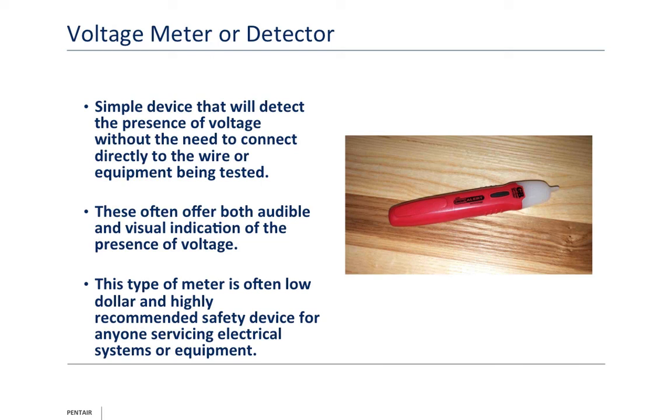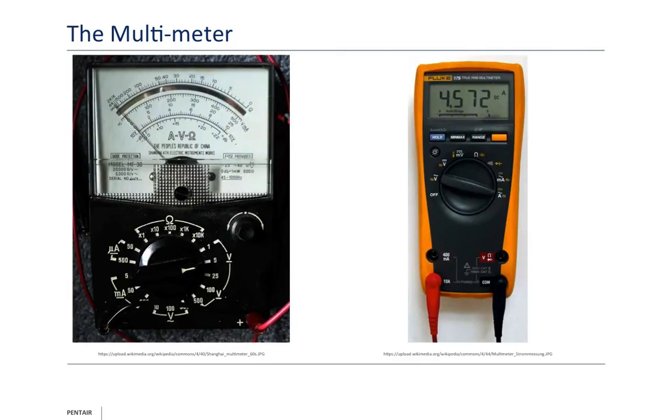When in doubt and you want to make sure, break out your voltmeter. The good old multimeters, there's plenty of them out there, from Fluke, which is one of the top ends, down to your Harbor Freight and your cheaper ones. In our industry, we need to buy a decent one. So when you're talking multimeters, you want one that can measure volts AC up to 600 volts, ideally, and are typically rated for Cat 3. Even though we don't do Cat 3 work, ideally, I would like to see my meter rated for up to Cat 3. That tells me it's better insulated.